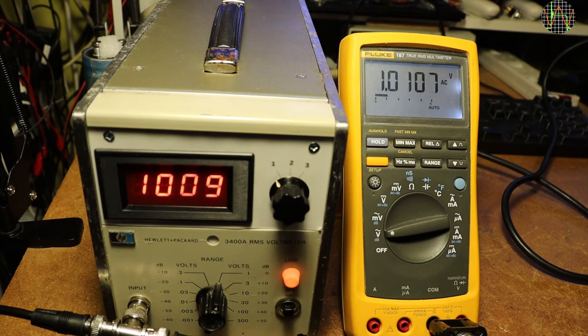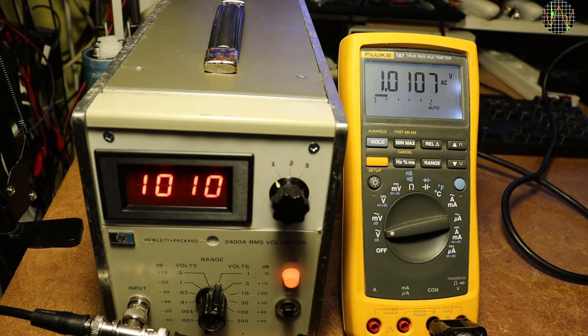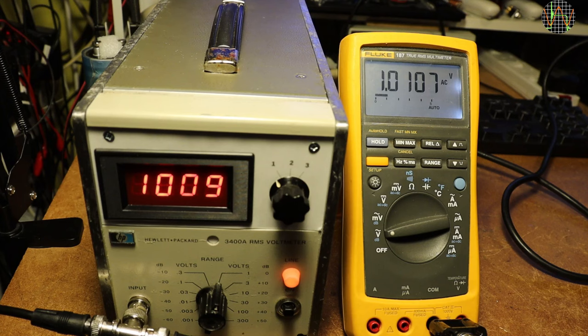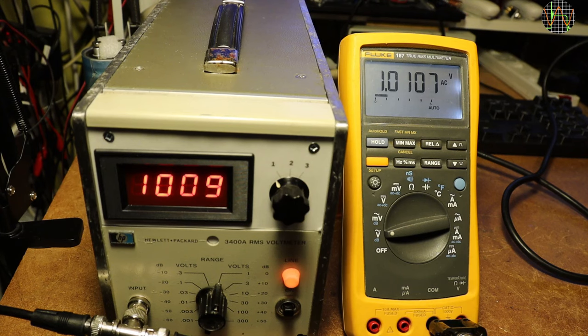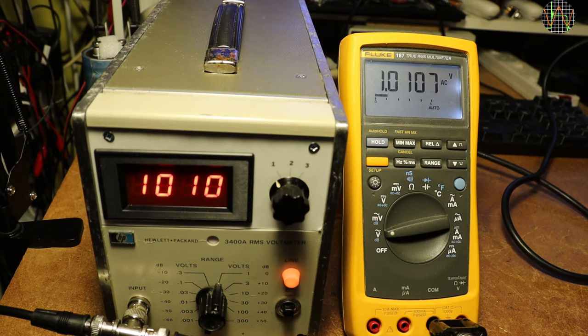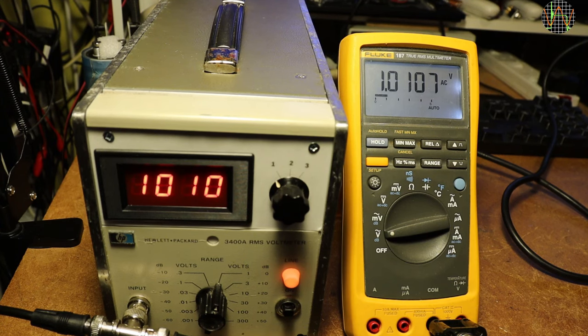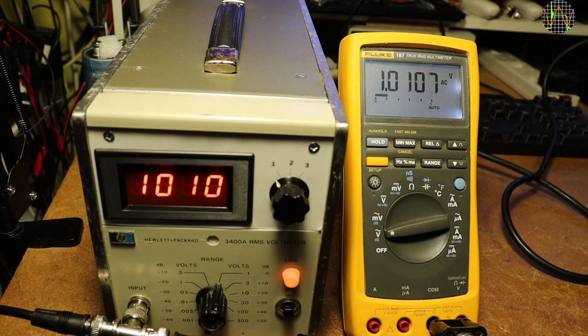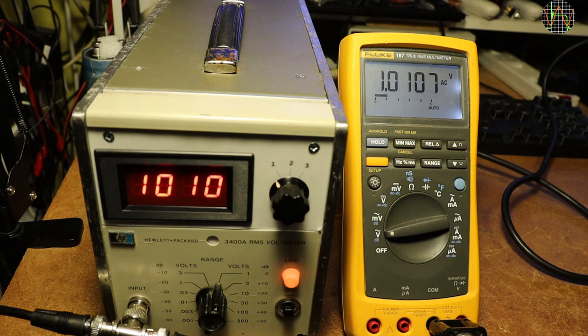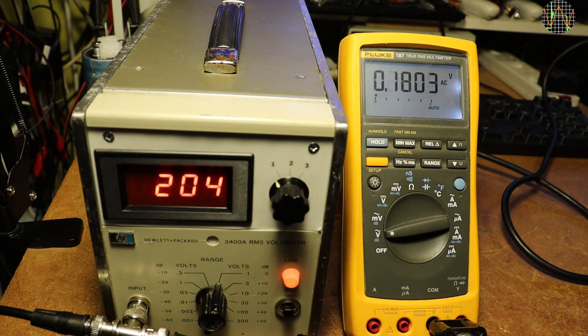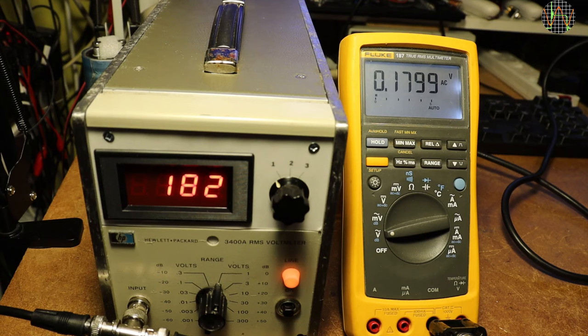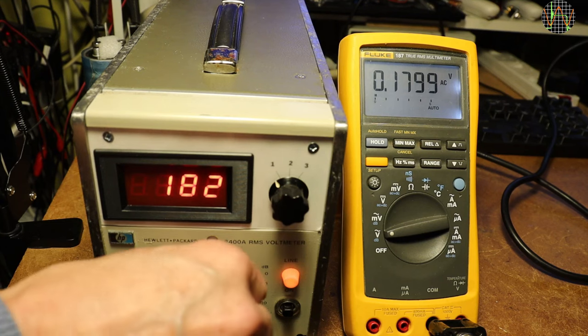Finally, a quick look at how the range switching works with the new display. In the 1V scale, the selector is on 1 and the display shows the voltage as a number. You need to be aware of where the decimal point should be yourself, so this is really 1.010V or thereabout. Dropping down to 180mV and after a while the HP3400A has adjusted. If I want to see better accuracy, I can switch to the 0.3V scale and put the selector to 2 because it is below 200mV.